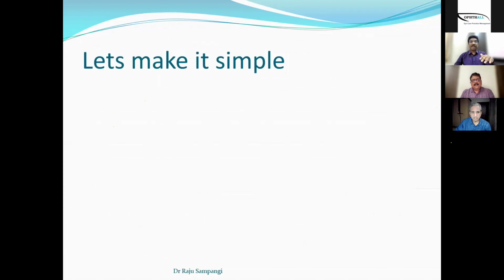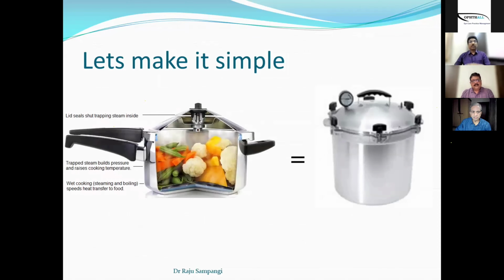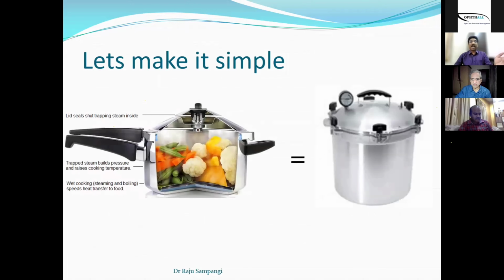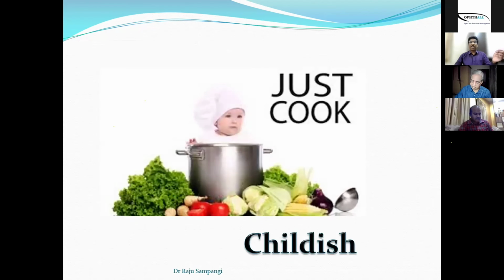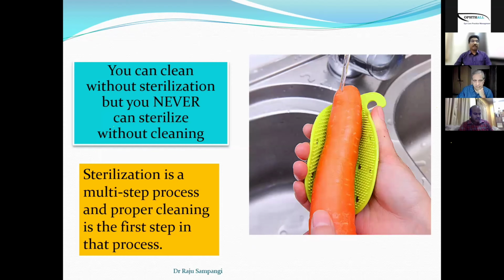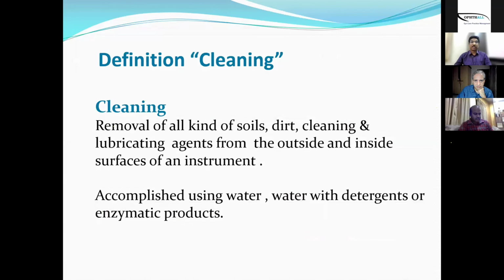Now, let me make it simple. Let me compare the sterilization process to cooking. You can clean without sterilizing, but you can never sterilize without cleaning. Sterilization is a multi-step process, and proper cleaning is the first step of that process. By cleaning, we try to remove all kinds of soil or dirt and whatever lubricating agents, if at all, we have used on the surfaces of the instruments. This is accomplished by water or water with detergents.